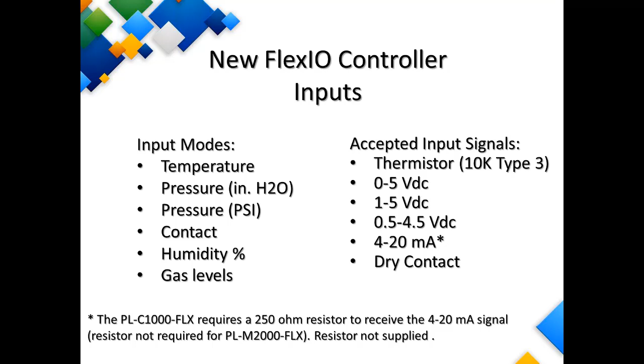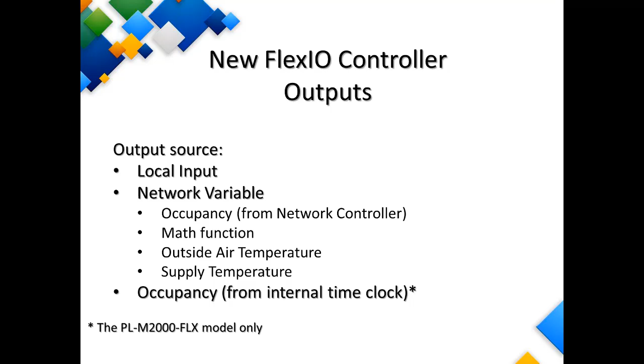We can use the outside air temperature as the source for our output. We can also use the supply temperature. So if you have some kind of rooftop unit and we're monitoring what the supply temperature is, well, we can use that as our source as well, so we don't have to install an extra sensor. And we can also drive an output based on the occupancy from the internal time clock on the controller. Now, just as a little reminder, this is applicable only for the M2000 because that one has an internal time clock embedded within it, whereas the C1000 does not have that time clock feature.